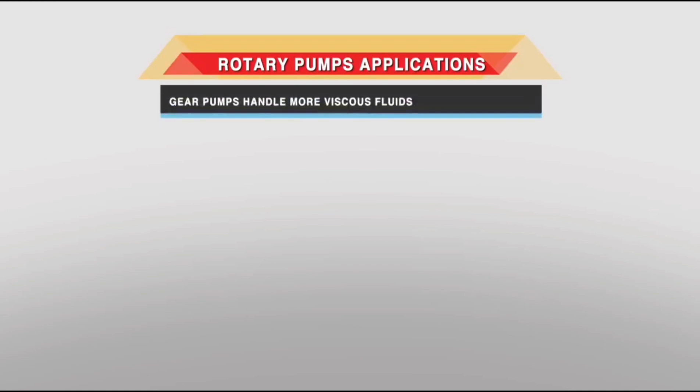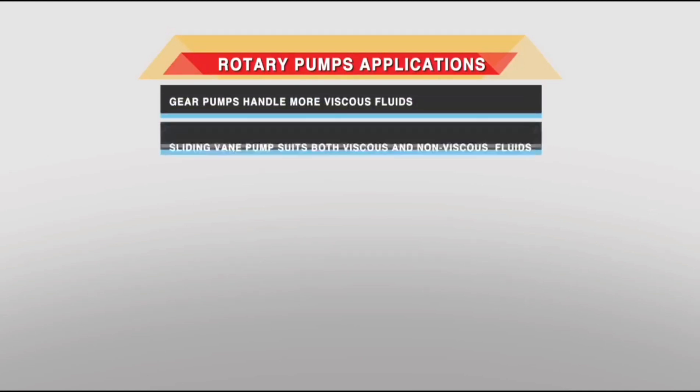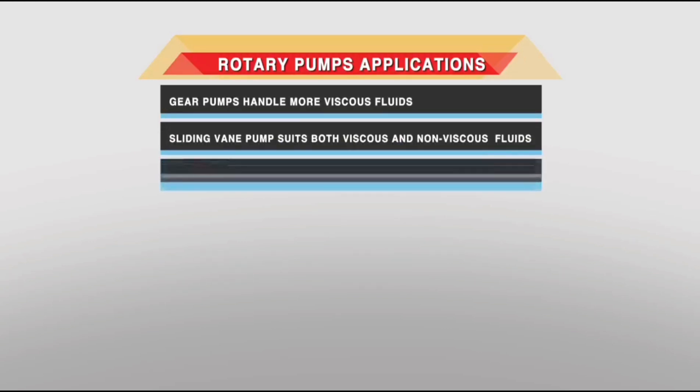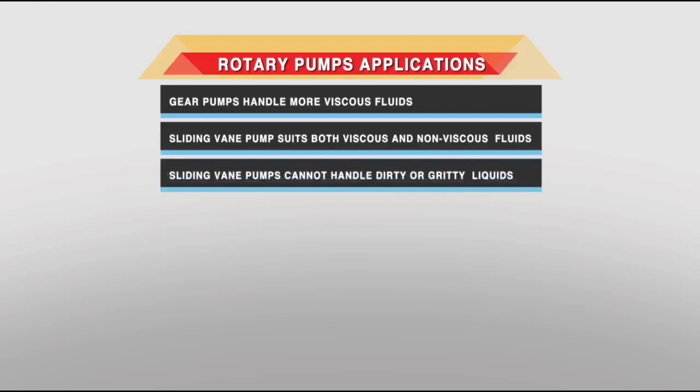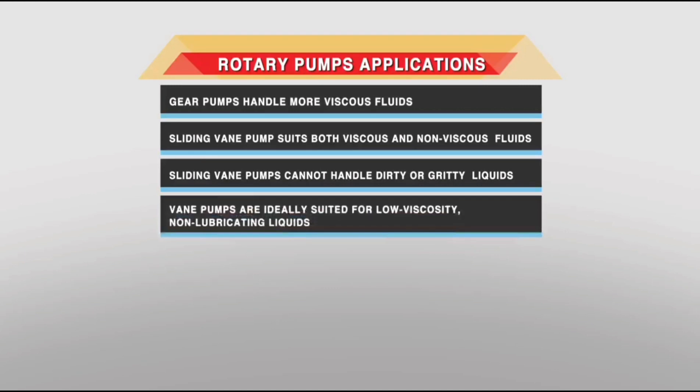Applications of rotary pumps are: Gear pumps handle more viscous fluids. The sliding vane pump suits both viscous and non-viscous fluids. Sliding vane pumps cannot handle dirty or gritty liquids. Vane pumps are ideally suited for low viscosity, non-lubricating liquids.